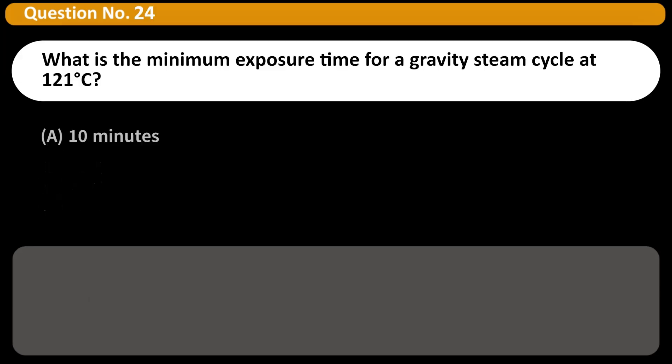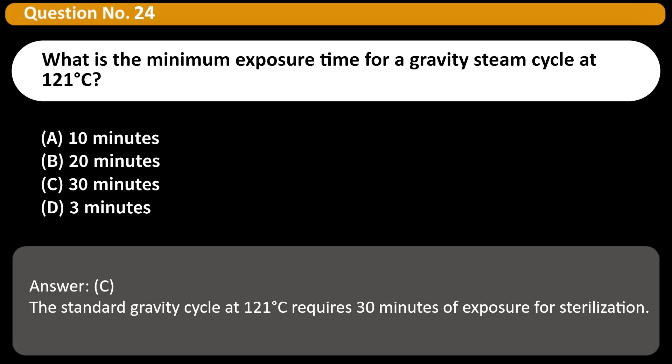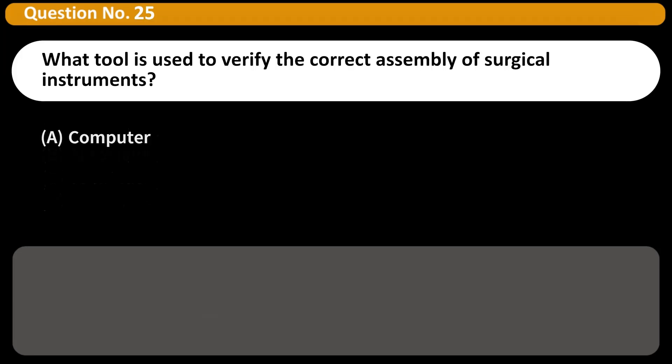What is the minimum exposure time for a gravity steam cycle at 121 degrees Celsius? A. 10 minutes, B. 20 minutes, C. 30 minutes, D. 3 minutes. Answer C. The standard gravity cycle at 121 degrees Celsius requires 30 minutes of exposure for sterilization.